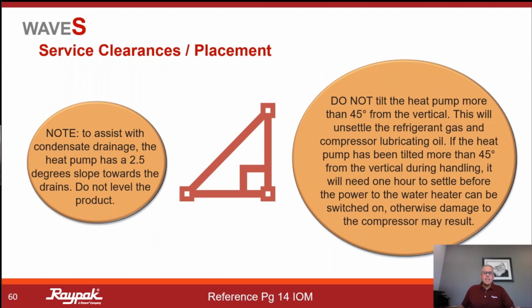Now, a couple of things as I was looking through the manual, I thought it important to include that the unit is built with some pitch to it, so that if it does go into a defrost, it will drain properly, right? So don't try and level the unit, just put it on a base that is level. Don't try to individually level that unit, if that makes sense.